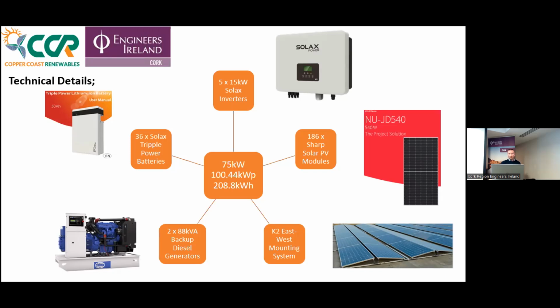They're hybrid and bi-directional. So it meant that we were able to couple the batteries on the DC side of the inverter. What that means is it was one less lot of AC infrastructure, but also that the inverter or the battery's maximum output will be limited to 75 kilowatts. If we AC coupled the batteries, we would have had additional controls in there, which we didn't want. We tried to keep it simple.